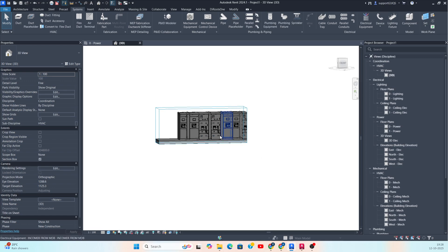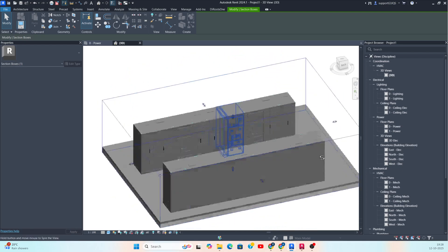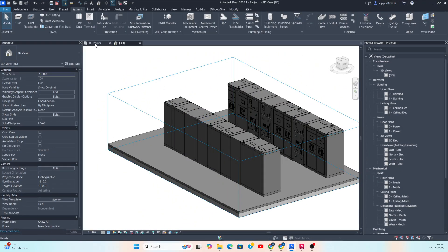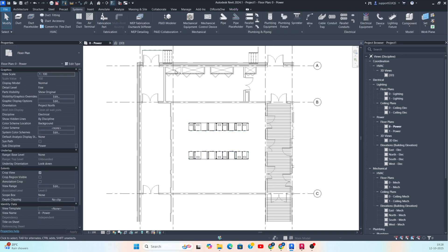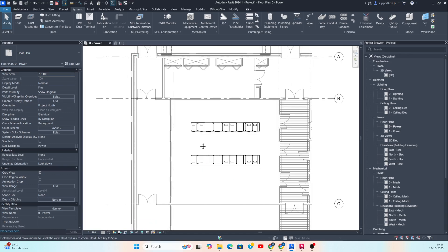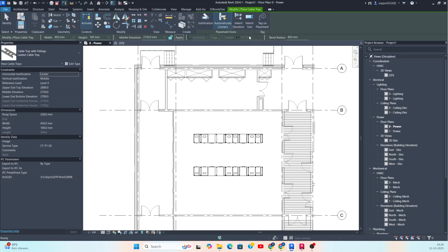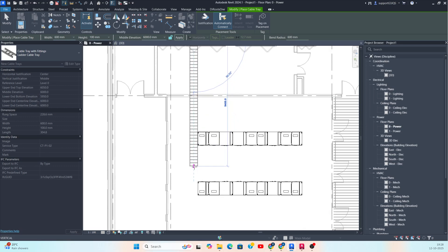If you look at the 3D view of the high voltage portal, what I am planning to do is run the cable channels — cable ladders. These are high voltage, so we need to run the cable ladders. I want to draw some cable ladders connecting to this ladder. Go to the cable tray section and choose cable ladders. The elevation I set is 6000, and the size of the cable ladders should be 600 after calculations. First, your cable ladders are made from here, connecting to this panel system like this.